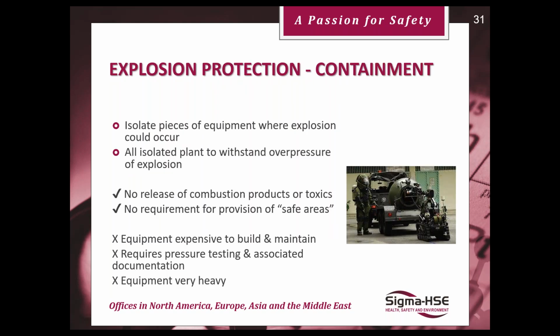Containment, building pressure vessels, basically has its good points, but of course also some very bad points: it can be very expensive. There'll be pressure equipment, so you'll have to deal with specific legislation and so on and so forth. It's more used on vapors and gases than on powders, but can be.